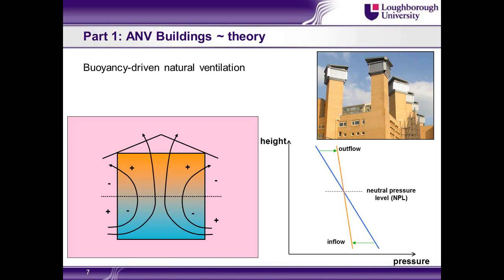So that all sounds a bit theoretical, but what happens in practice is we have to make sure that we get that level higher than all of the inlets and lower than all of the outlets. So we've got to size our ventilation openings to position that neutral pressure level in the right place. So we can control that based on how we design the natural ventilation system. I'll come back to that in a practical example a bit later on and show you how it plays out and how it can cause a problem.